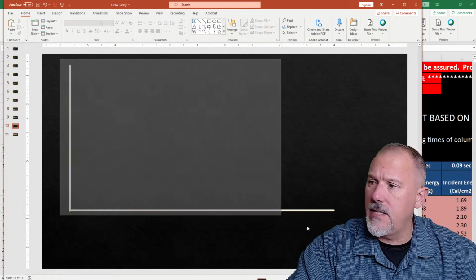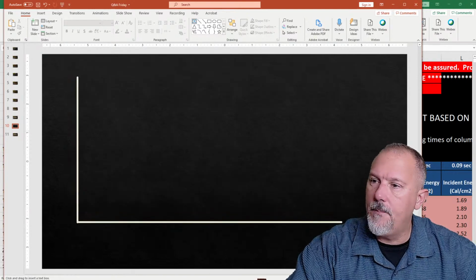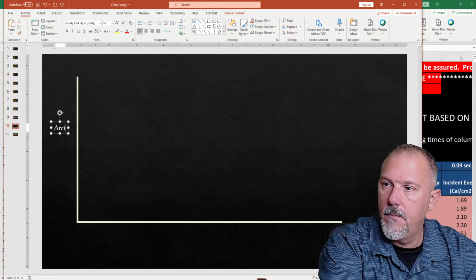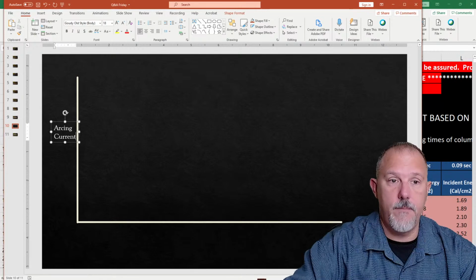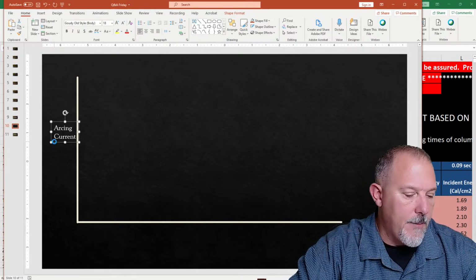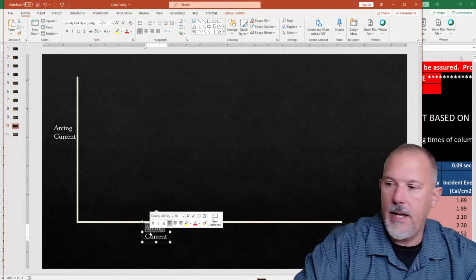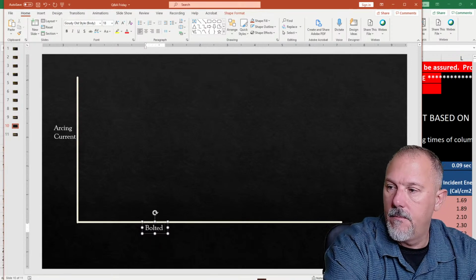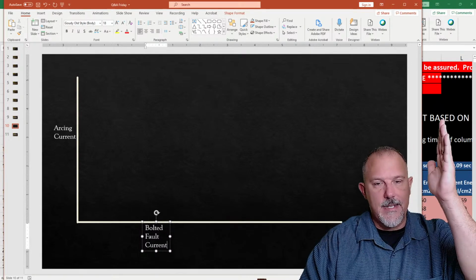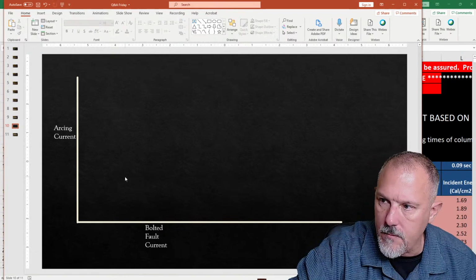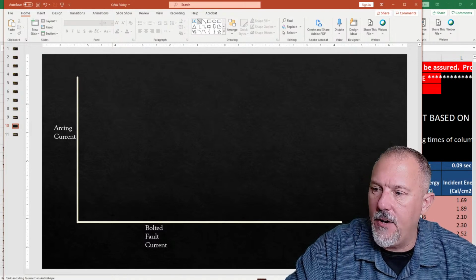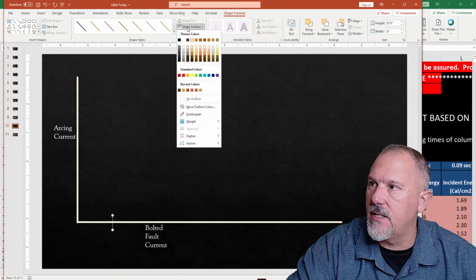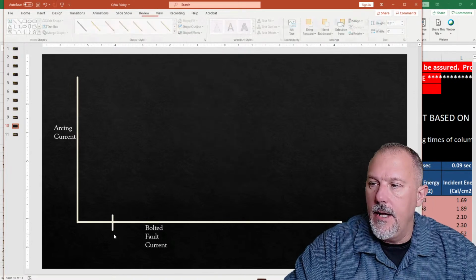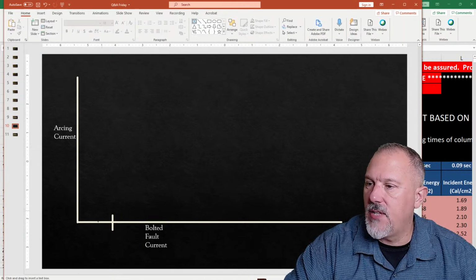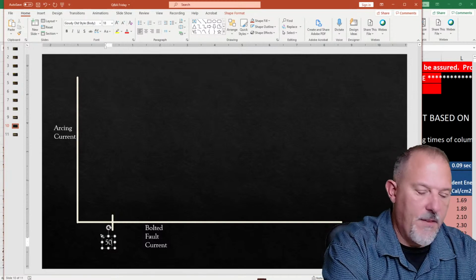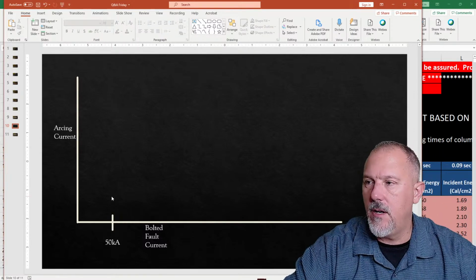So what he did was he said, okay, up this side we're going to have arcing current. This is a very crude way of showing it, but I'm going to cut a lot of the detail out. And this is bolted fault current. So up this axis, I have arcing current. Across the bottom, I have bolted fault current. Now, for any given value of bolted fault current, let's say I have this point right here, and we're just going to say this is 50,000 amps of bolted fault current.